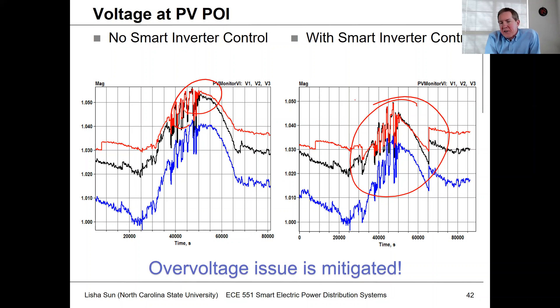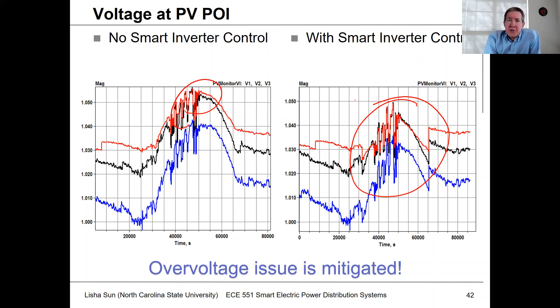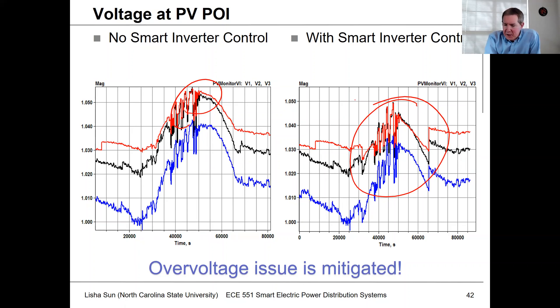The downside of this control is that if it's absorbing a lot of vars, those vars have to come from somewhere — maybe from a local capacitor bank, or maybe from the transmission grid. If they come from the transmission grid, we're causing additional issues there. So it's not a perfect solution, and you have to make sure you don't overuse this capability.